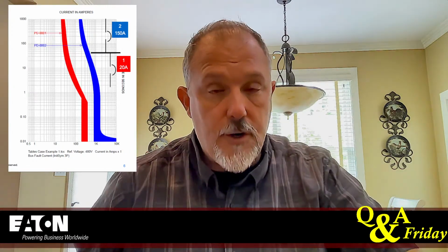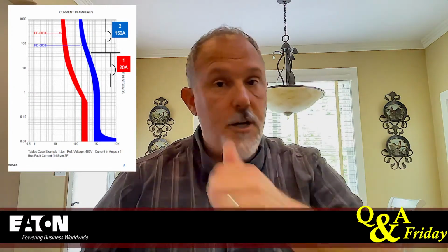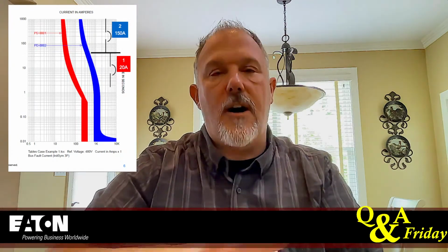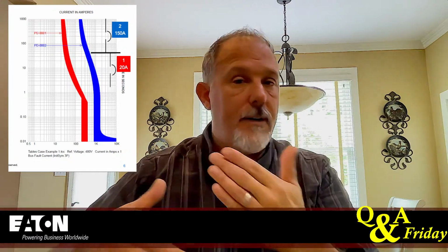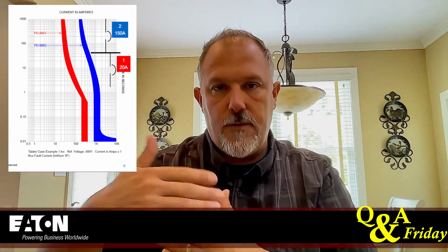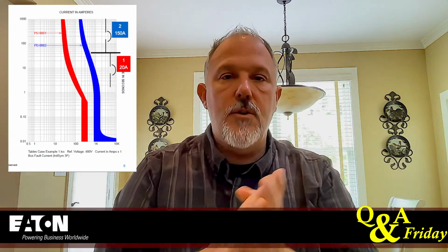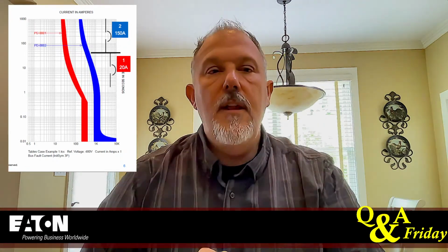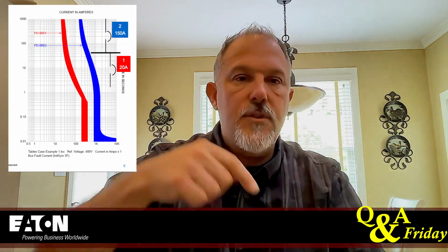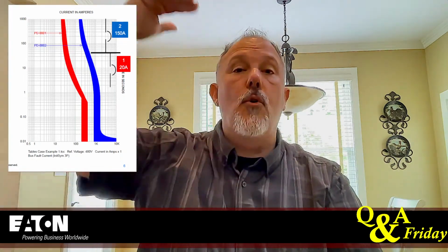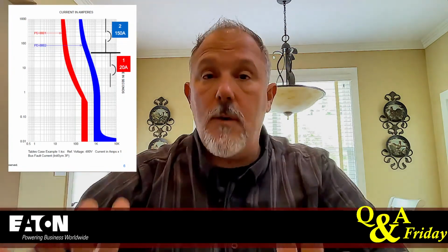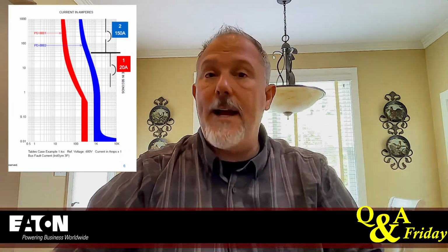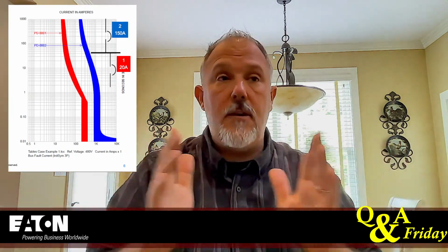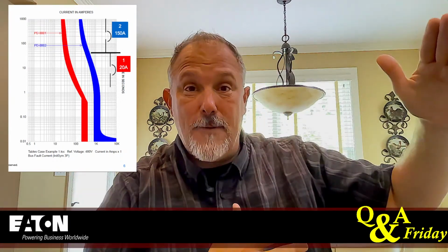You don't need to know the fault current. You're maintaining a 2-to-1 ratio. Whatever the ratio says, most often it's 2-to-1. Depending upon the fuses that you're using, you might have different ratios, a 4-to-1 ratio or whatever. But most commonly it's a 2-to-1 ratio. If I've got a 20 amp fuse downstream, I can use a 40 amp or greater upstream, up to 200,000 amps. I don't care. I don't need to plot any curves. That'll work over the full range, because there's no adjustability on a fuse, right?